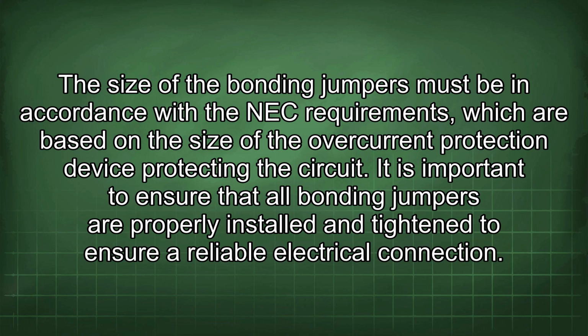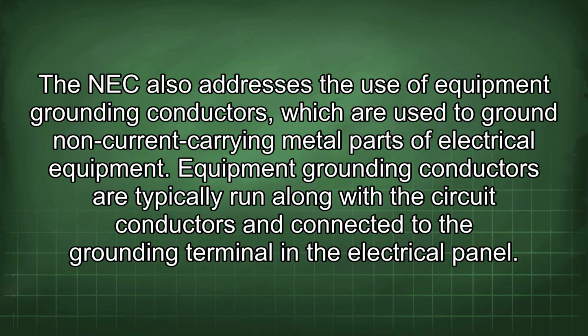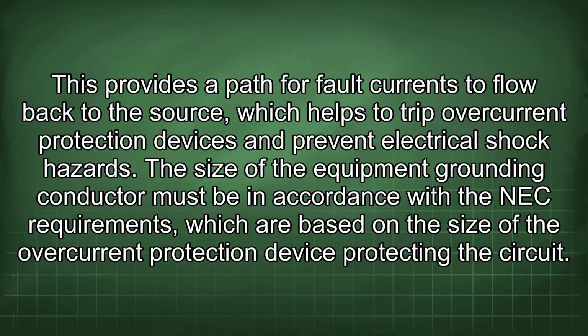It is important to ensure that all bonding jumpers are properly installed and tightened to ensure a reliable electrical connection. The NEC also addresses the use of equipment grounding conductors, which are used to ground non-current carrying metal parts of electrical equipment. Equipment grounding conductors are typically run along with the circuit conductors and connected to the grounding terminal in the electrical panel. This provides a path for fault currents to flow back to the source, which helps to trip overcurrent protection devices and prevent electrical shock hazards.